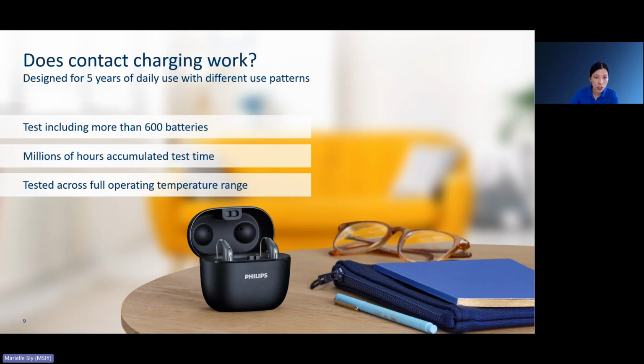And before we launched the charger and the hearing aids, we tested more than 600 batteries, millions of hours of accumulated test time, testing across the full operating temperature range to make sure that it still charges effectively without degrading the quality of the battery. And we tested it for the equivalent of 5 years of daily use. So this is not a theoretical design. We actually made sure to validate this in real world conditions in a wide variety of different usage patterns, with streaming, without streaming, with a large amplification, with little amplification. So the technology is really reliable, and it's designed to be one step above inductive charging from the traditional hearing aid families we've had.